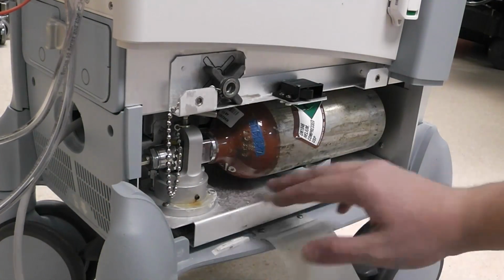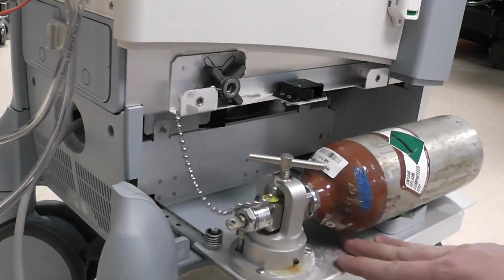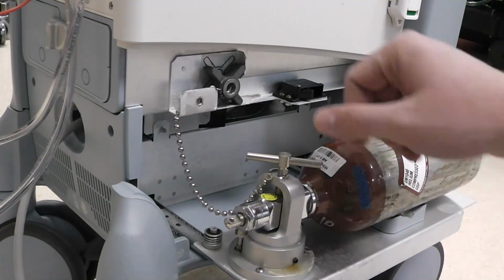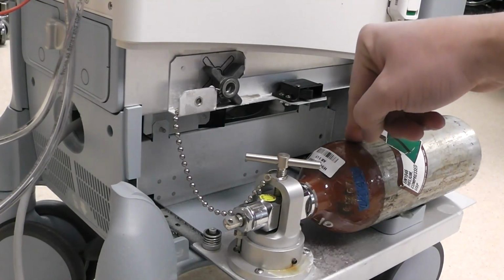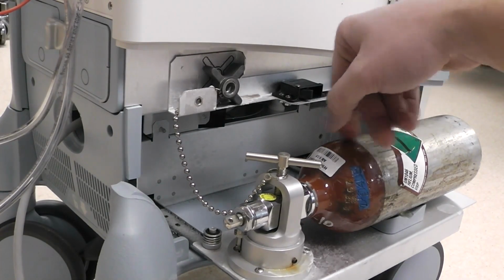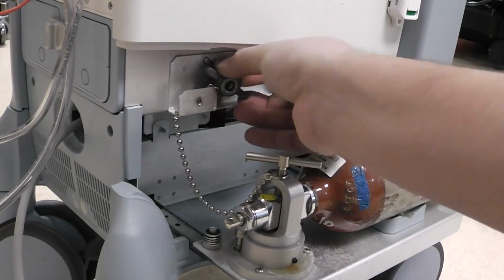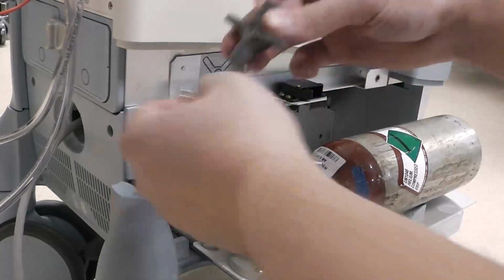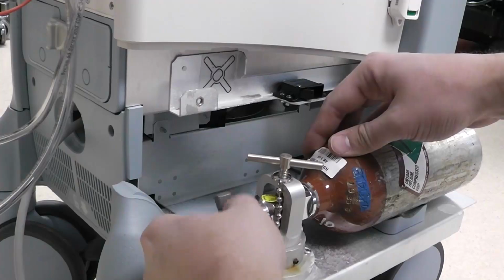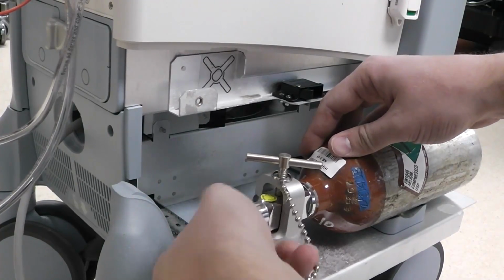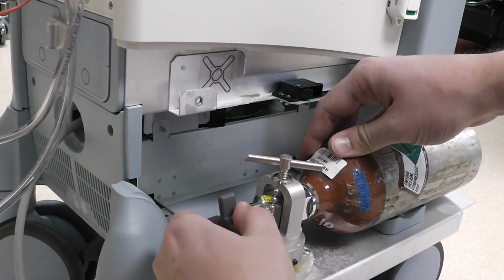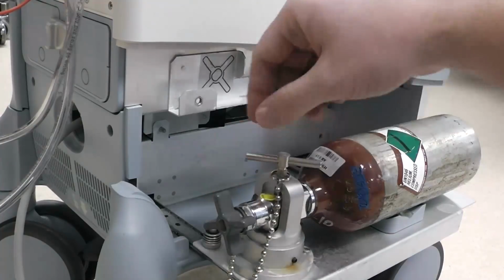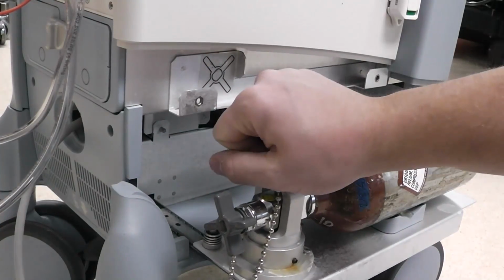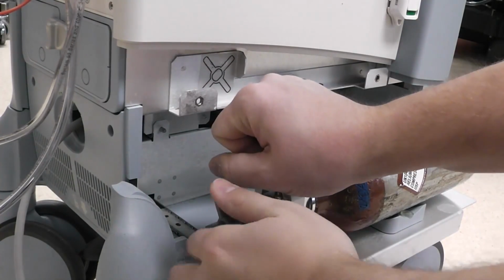This side compartment pulls straight off, and then there's a little shelf here that pulls out. Before you remove this tank, you need to make sure that the helium is shut off. So you remove this little handle here and tighten this all the way to shut off the flow of helium. Make sure that's shut off, and now you can open up the hand crank. You will hear some gas being released as you do that.